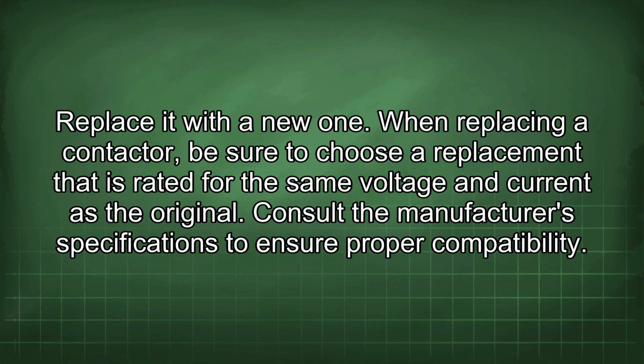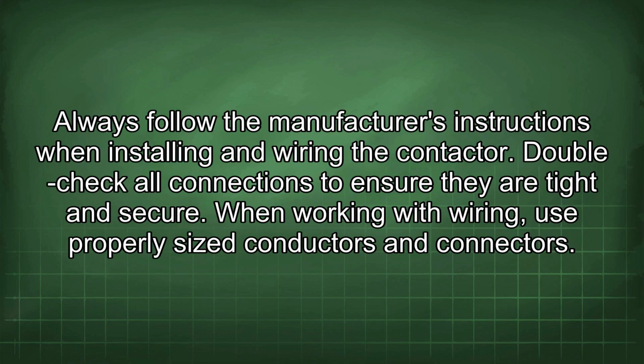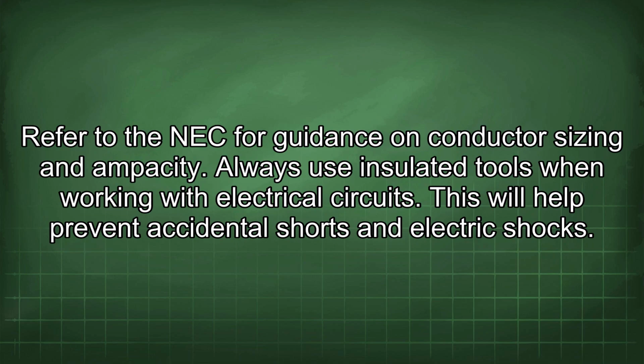When replacing a contactor, be sure to choose a replacement that is rated for the same voltage and current as the original. Consult the manufacturer's specifications to ensure proper compatibility. Always follow the manufacturer's instructions when installing and wiring the contactor. Double-check all connections to ensure they are tight and secure. When working with wiring, use properly sized conductors and connectors. Refer to the NEC for guidance on conductor sizing and ampacity. Always use insulated tools when working with electrical circuits. This will help prevent accidental shorts and electric shocks.